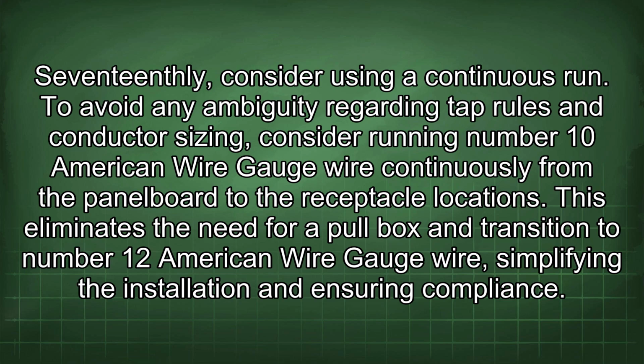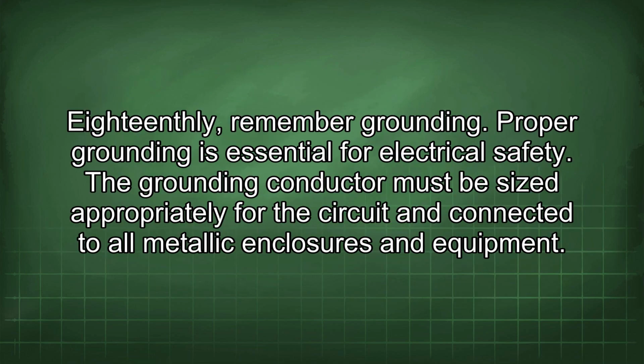17thly, consider using a continuous run. To avoid any ambiguity regarding tap rules and conductor sizing, consider running number 10 American wire gauge wire continuously from the panel board to the receptacle locations. This eliminates the need for a pull box and transition to number 12 American wire gauge wire, simplifying the installation and ensuring compliance.